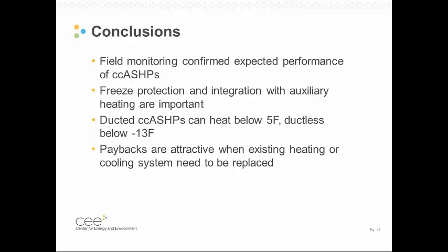And in conclusion, when the heat pump was on, it worked great as we would expect. Really good performance. The big variability in all of this is how much freeze protection and how well you integrate it with the backup. Those can be done very well if you follow the guidelines we put forward here. The systems do work at cold temperatures, and if you stage the install right, the systems can be really attractive.